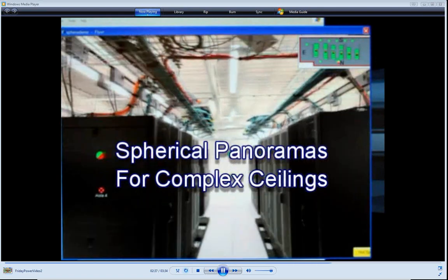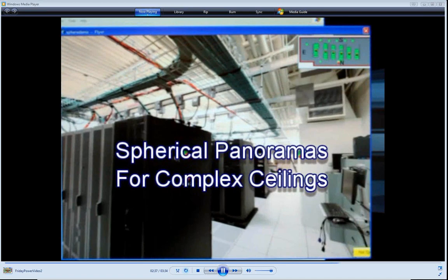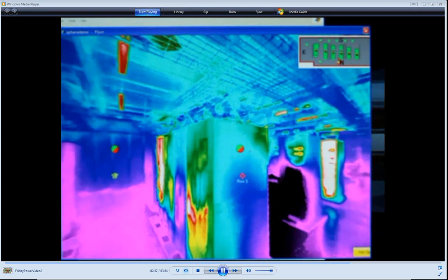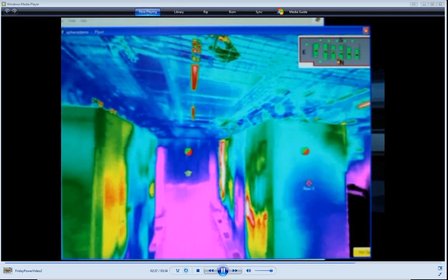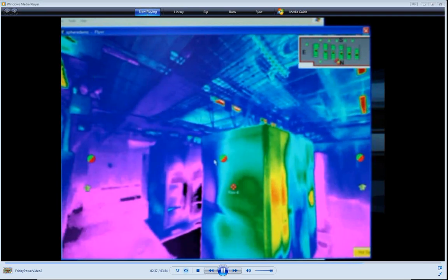In another image, servers functioned normally but a router had been placed in each rack to make wiring easy — resulting in those routers using server exhaust air as intake, operating at very high temperatures. This single image identified a failure situation threatening $32 million in equipment. Documenting complex 3D ceilings uses spherical panoramic images, allowing issues to be identified in areas between the ceiling and server tops.